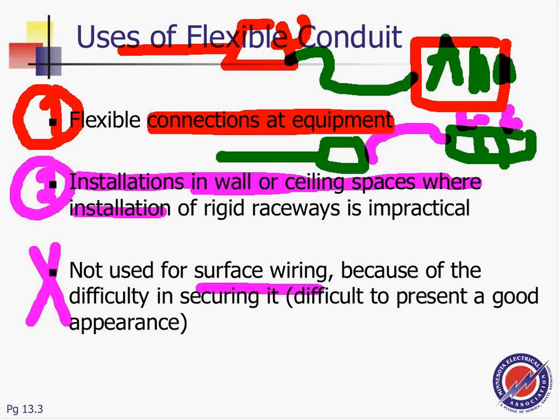So these are basically where you don't want to use it. It's not used for surface wiring, because it looks so heavy. So this is not a conduit that you're going to use for surface mounting equipment. You're not going to surface mount it for feeders and branch circuits and so forth, because it's not as neatly laid out and bent as EMT, rigid, or any other conduits. Anything else about the use of the flexible conduits? Any flex, anytime. It's not just metallic, it could be the non-metallic or the liquid type. Any questions? And so really, if I'm to emphasize one thing, it's really tying to equipment, and sometimes it could be handy when it comes to fishing in a wall conduit.